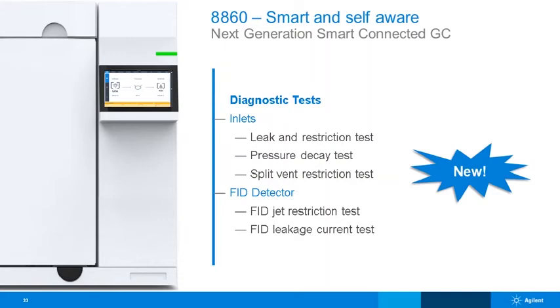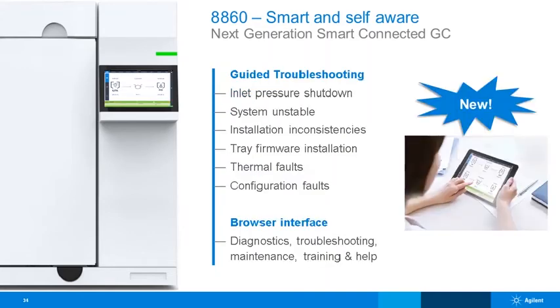So in the past, you'd have a problem with the tubing from your split vent getting blocked, and you didn't know that until you undid it and checked whether there was dirt in there. Now the actual instrument would test and would tell you there's a problem. And if you look at the FID as well, FID jets were being changed when they didn't need to be. Here we have an FID jet restriction test, and also a leakage current test. So these are all very new features that are unique to these new intelligent instruments.